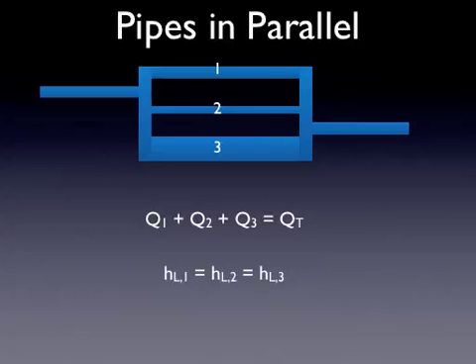This one is not obvious to me. You can derive it if you do conservation of energy carefully through the system. But just remember that for pipes in parallel, the way the water distributes the flow through those junctions is it makes sure that the head loss is the same in those three pipes. Water always takes the easiest path it can. And the way that works out mathematically is that the head losses have to be the same in each of those three pipes.